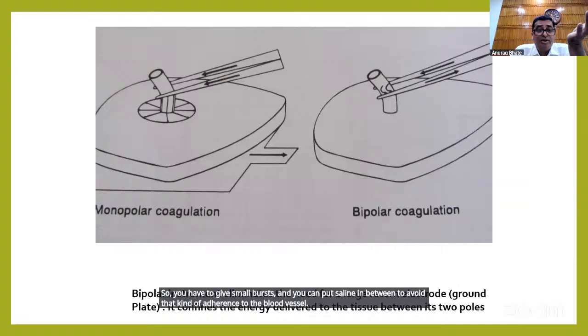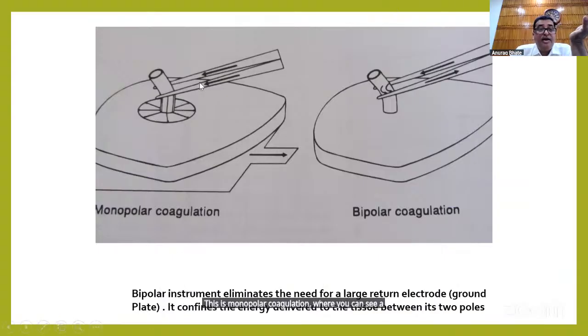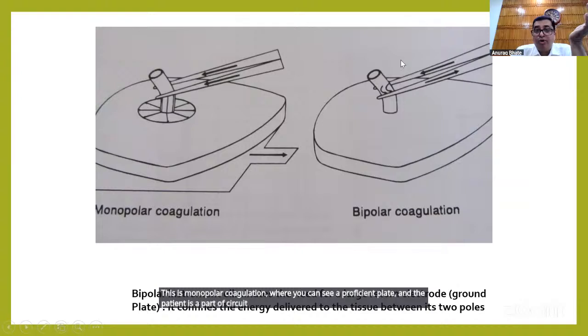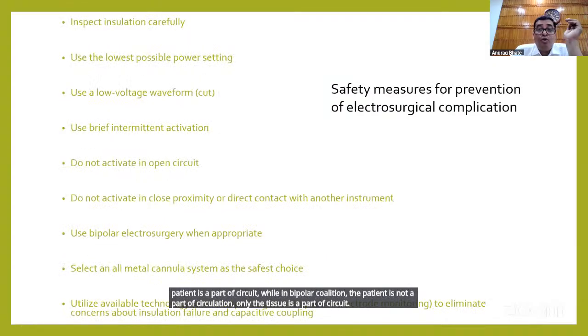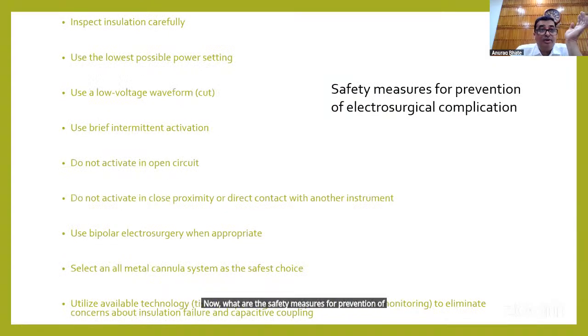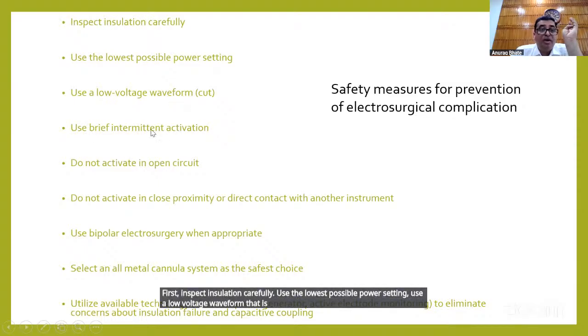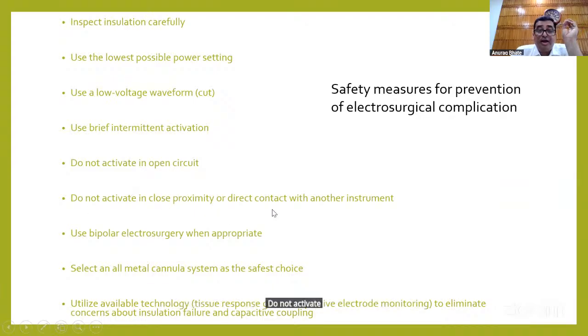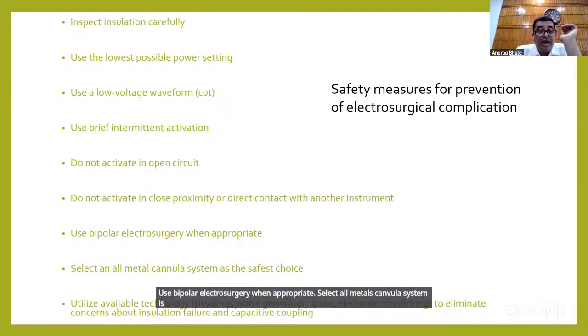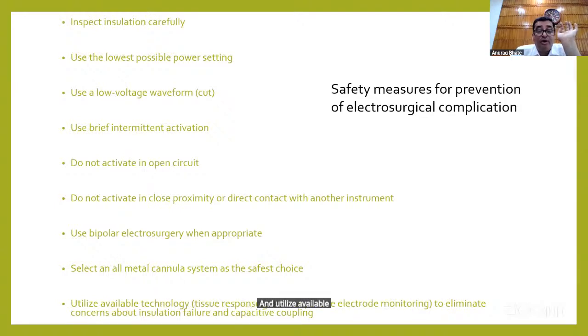This is monopolar coagulation, where you can see a patient plate and the patient is a part of circuit. While in bipolar coagulation, the patient is not a part of circuit, only the tissue is a part of circuit. Now, what are the safety measures for prevention of electrosurgical complications? First, inspect insulation carefully. Use the lowest possible power setting. Use a low voltage waveform that is cut. Use brief intermittent activation. Do not activate in open circuit. Do not activate in close proximity or direct contact with another instrument. Use bipolar electrosurgery when appropriate. Select all metal cannula system as safest choice and utilize available technology to eliminate whatever the concerns are there.